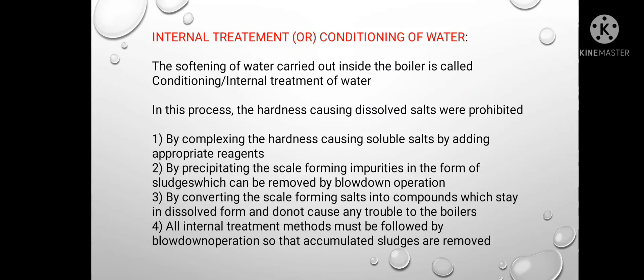Now we will see internal treatment, also known as conditioning of water. The softening of water carried out inside the boiler is called conditioning or internal treatment of water. In this process, the hardness-causing dissolved salts are controlled: first, by complexing the hardness-causing soluble salts by adding an appropriate reagent; second, by precipitating the scale-forming impurities as sludges which can be removed by blow-down operation; third, by converting scale-forming compounds into compounds that stay in dissolved form and do not cause any trouble to the boilers.